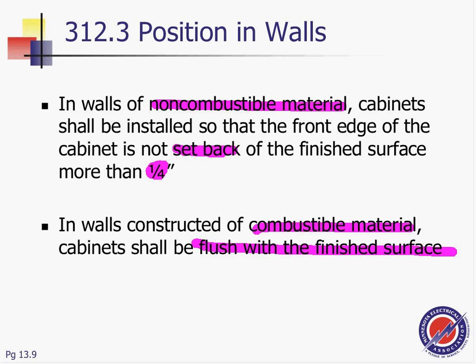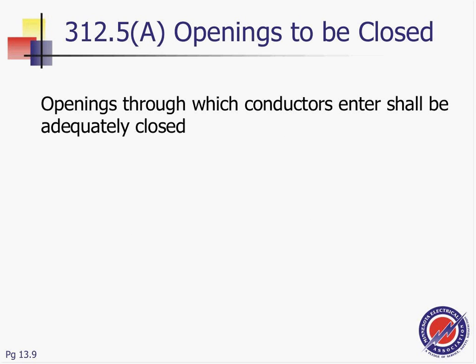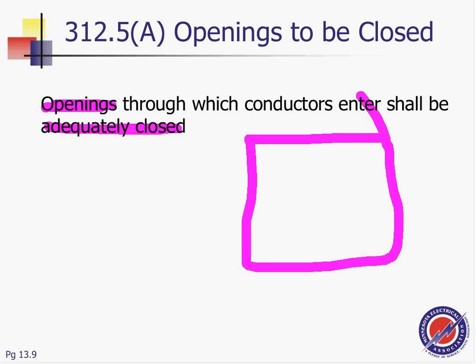That's for the types of cabinets, guys. They also must be closed, and I'm sure the inspector has called you on this a couple of times. If you have any openings through which conductors enter, they shall be adequately closed. So if you have an opening in the box and you do not use that particular opening, you have to go ahead and enclose it.